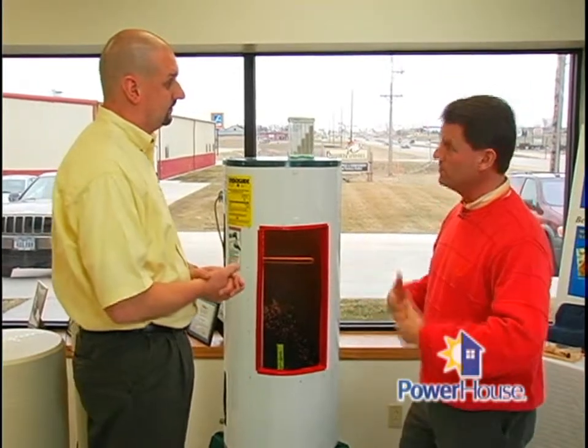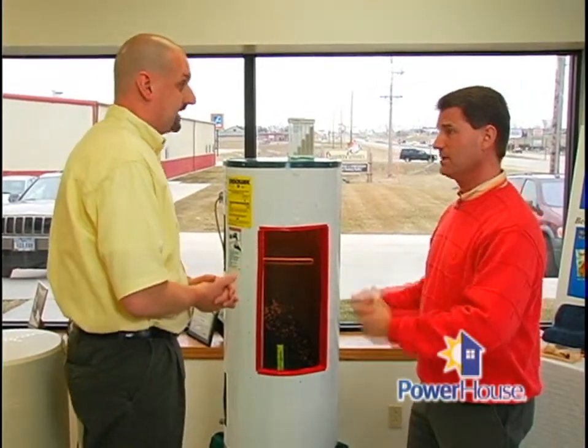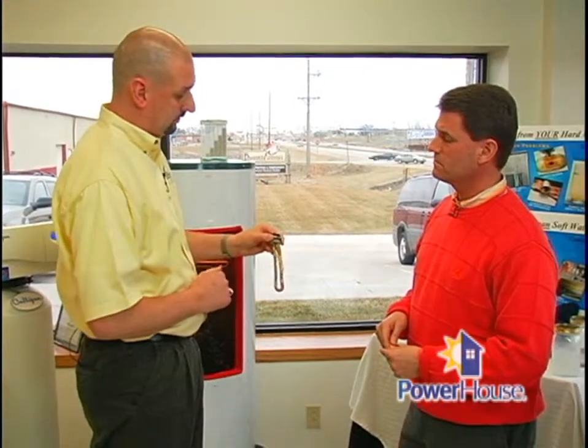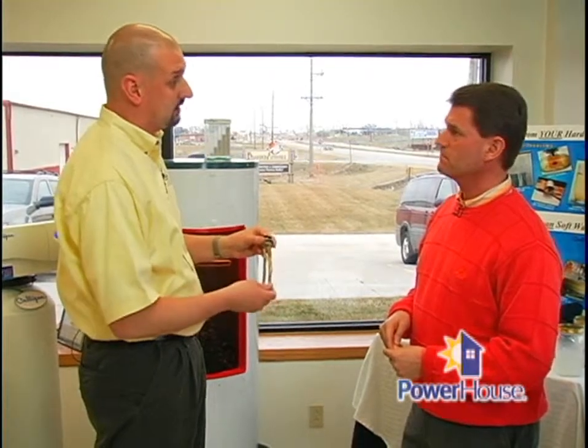As we talk about energy consumption, I've got to use more energy to heat my water. There are well-known studies, including one from the Water Quality Association — New Mexico State University did a study on energy consumption with hard water. What they find is that energy consumption is about 30% higher on a hard water supply than it is with soft water. That hard water starts to scale up on the heating element itself. This is a heating element we pulled out of a customer's water heater — scale builds up on that element, and the heating element has to heat the rock first, then the water. You'll see an average 30% higher energy usage because of that scale buildup.